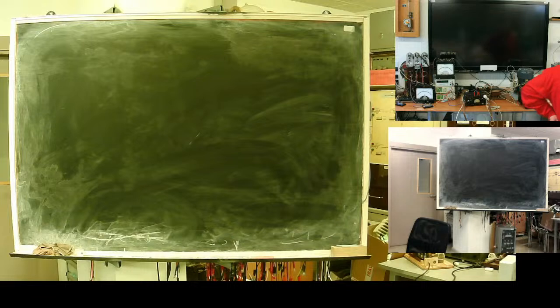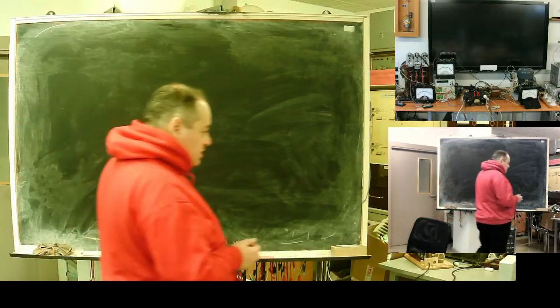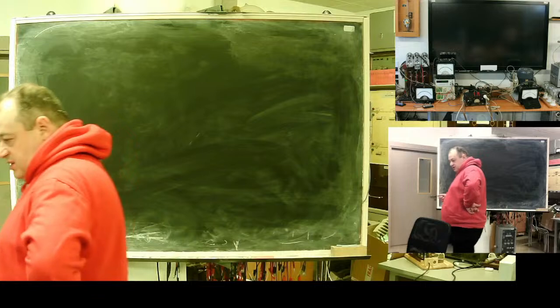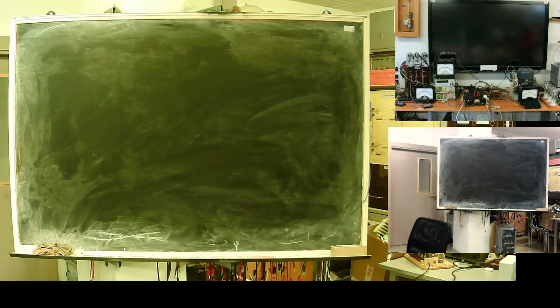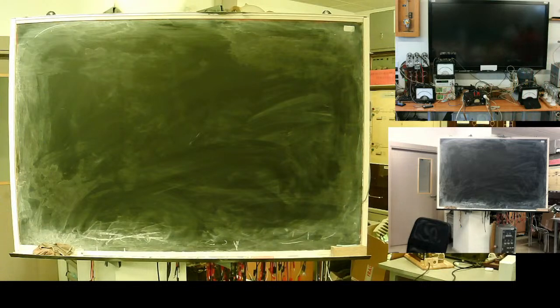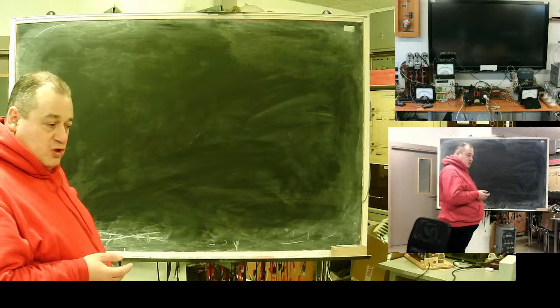But there is one problem. When a line is interrupted, one of the phases interrupted, we observe voltage asymmetry at a load. If our load is a rotating machine, generator or motor, this asymmetry causes an overheating danger to this machine. For generators, negative sequence voltage over 10% of direct sequence is a reason for immediate shutdown. It's an emergency situation. For a synchronous machine, approximately 7 to 10% pose a real danger of overheating and burnout.